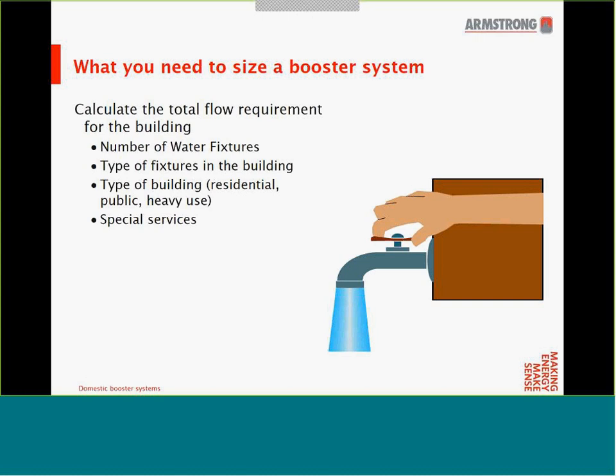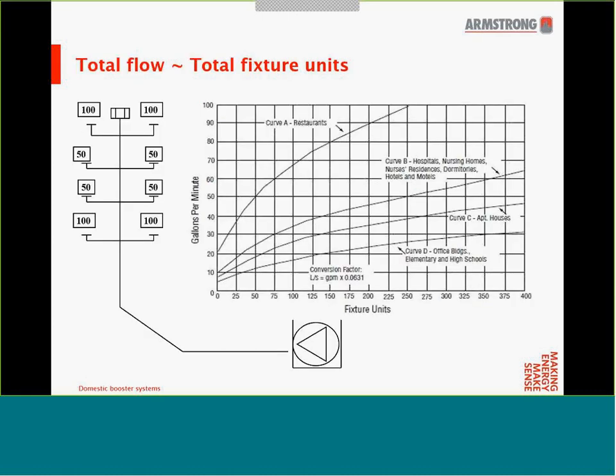Then we need to know what each fixture is — is it a toilet, a faucet, a valve, etc. We need to determine what type of building we're designing for: is it a residential building, public building, heavy-use building, or restaurants, for example. And lastly, we need to determine if there are any special services. One might be inclined to add up the required flow for each individual fixture and total them up, but this would lead to oversizing. Research shows it's possible to determine flow requirements from knowing the number of fixture units and the type of building.